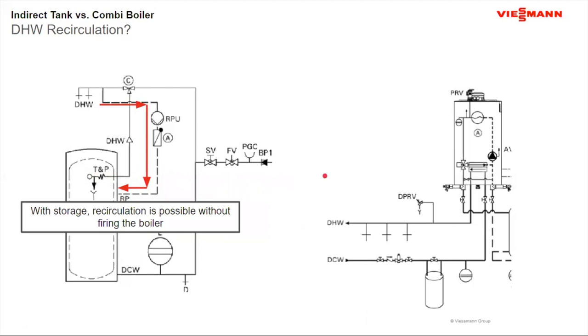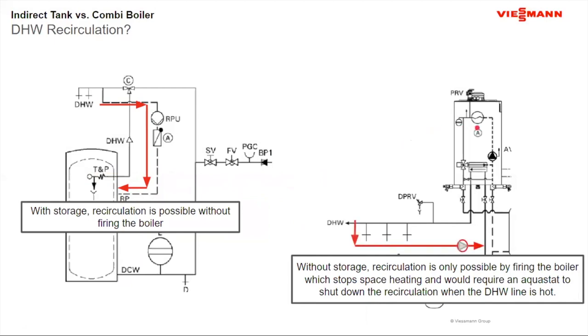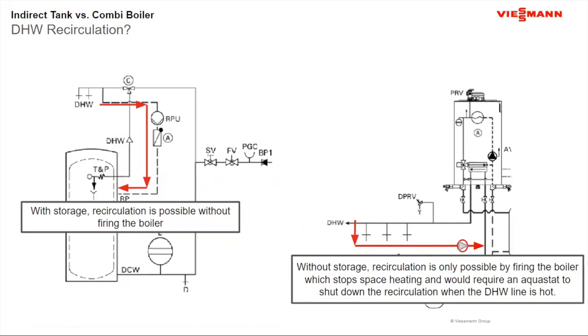Now over here, if I do a combi for domestic hot water recirculation, I can recirculate. But the problem is whenever that pump is running, the boiler is now shifted over to domestic hot water priority and shuts the space heating down. So I certainly can't have a system where that pump runs 24 hours a day. I'm going to put that pump on an aquastat, and it's going to cycle. When the pump comes on, the boiler goes into priority, generates domestic hot water, runs until that aquastat is satisfied, shuts the pump off, and then it does it again.